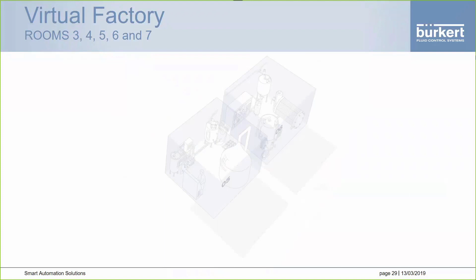The reason I've chosen all of these particular rooms is that in all of these areas, they're generally the sort of applications where we have a large cluster of on-off process valves or even modulating control valves. The important point here is that all of these devices are mounted really close to each other. A lot of the time they're in washdown zones, and therefore it makes a lot more sense than housing the pneumatics back in distributed or even centralised panels.